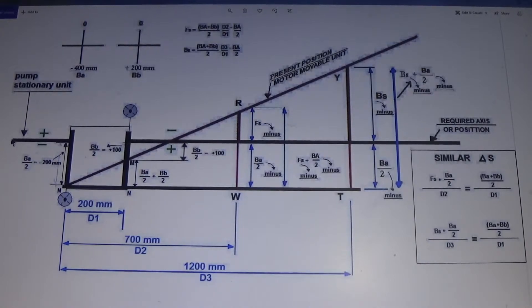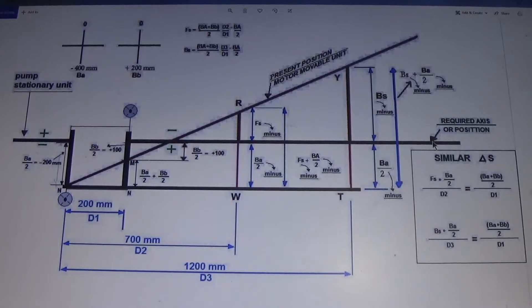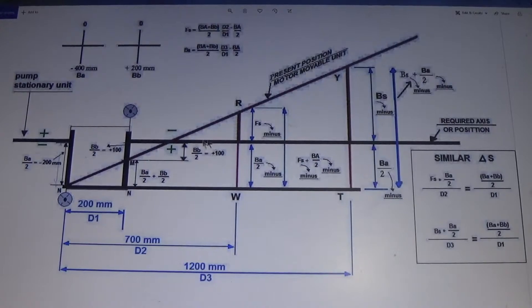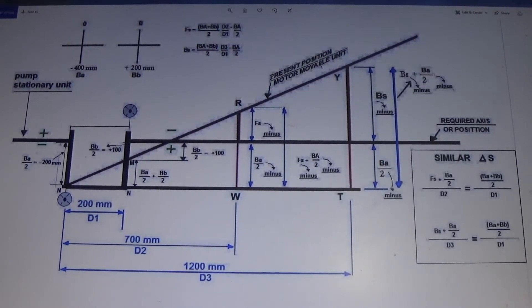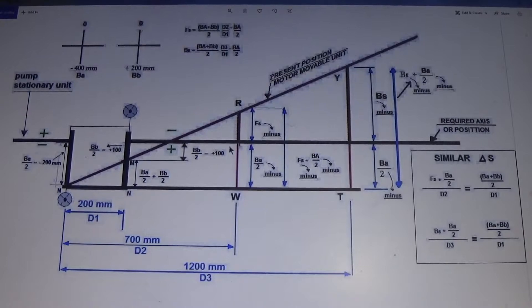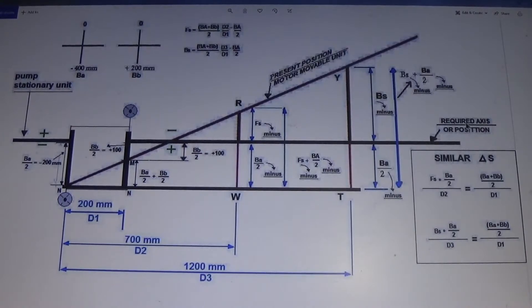This is your pump, which is the stationary unit — here you don't add or remove shims. This side is the motor, which is movable. This is the required position and this is the present position. Your motor shaft is passing from here, and this motor is the movable unit where you are going to add or remove the shims. This is your present position and this is your required position.